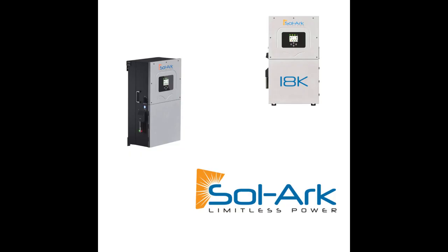One of the big things is non-export, right? So we are a PCS certified inverter. We have external CTs, which can allow us to monitor upstream loads to offset, especially for peak shaving, a very typical use case. But then also non-export, you're not wasting that power, sending that back out to the utility when you could be using it for other things, or putting power in the battery. And sometimes you just want to say no to the utility. I'm not going to send you my power, so you don't have to, right?